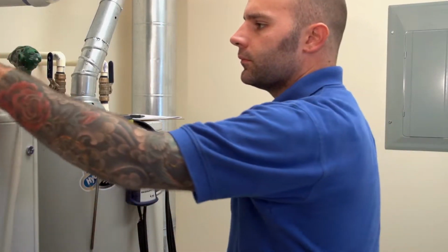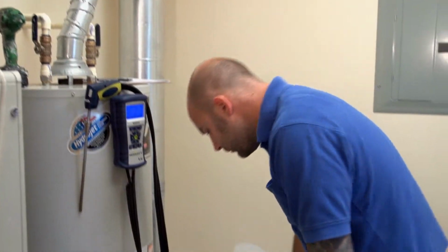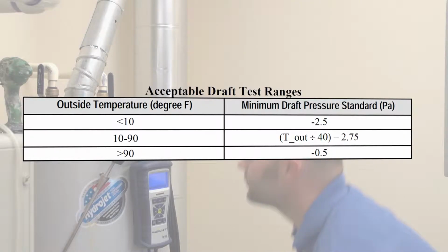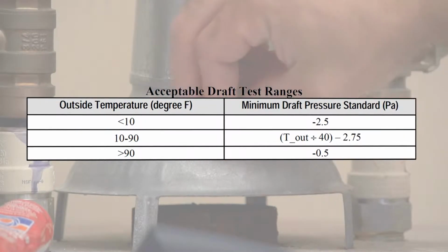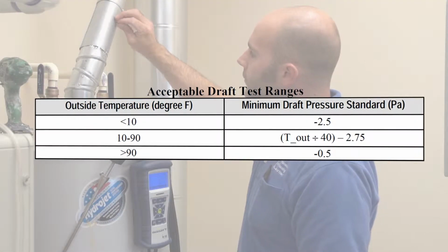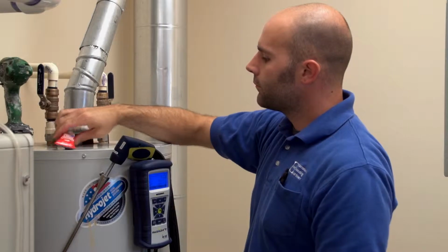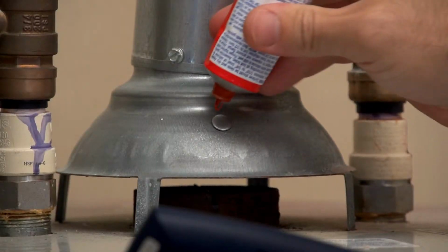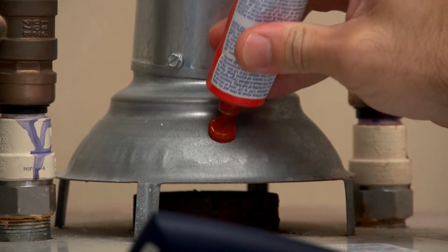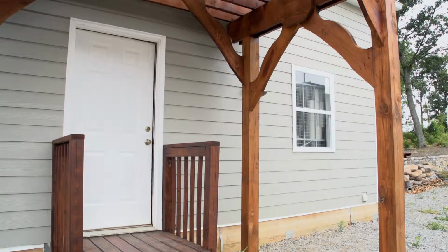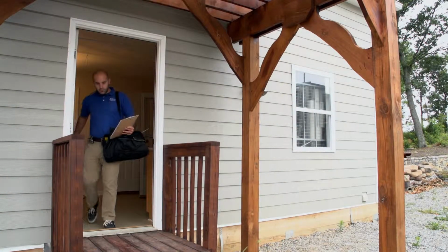Return the house to normal operating state, taking note to readjust the settings on the water heater to pre-test conditions or recommended levels. Compare the test results for spillage, draft, and CO to the diagnostic tables from BPI or your local standards. At this point, you may repair and patch the holes used for testing using plugs and high-temperature RTV sealant. Use the test results to devise a weatherization strategy that will encompass the dynamics of the combustion device and ensure a safe operating environment.